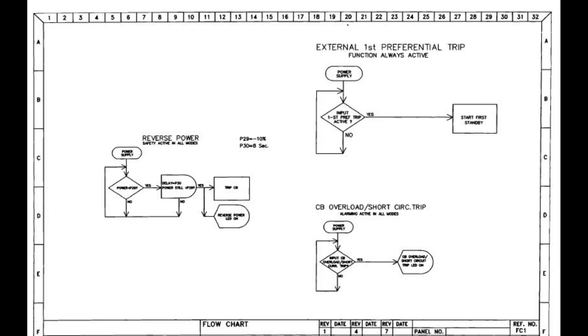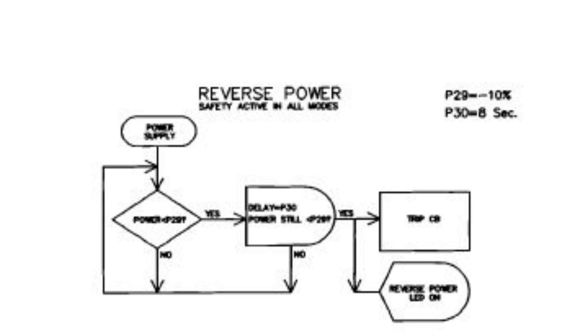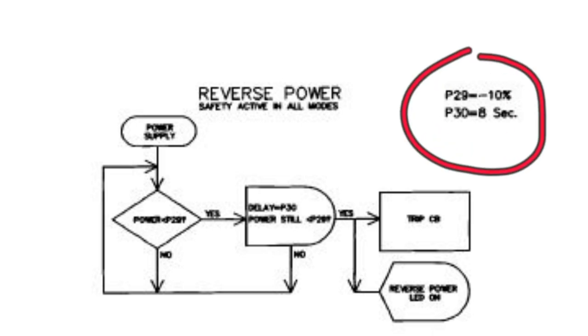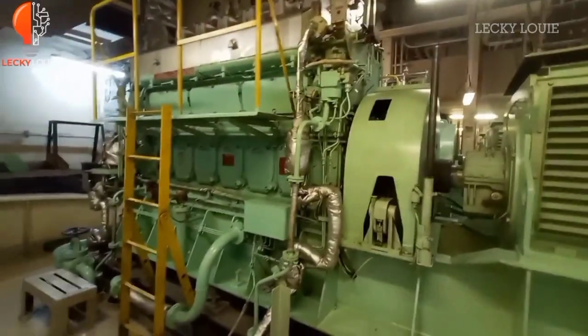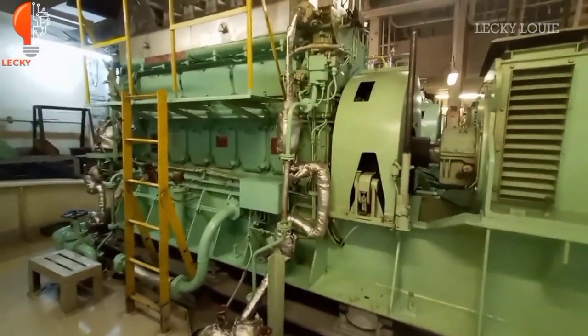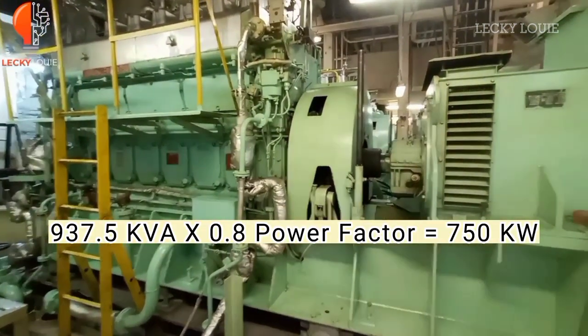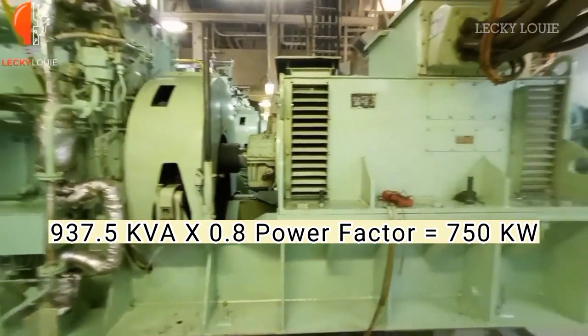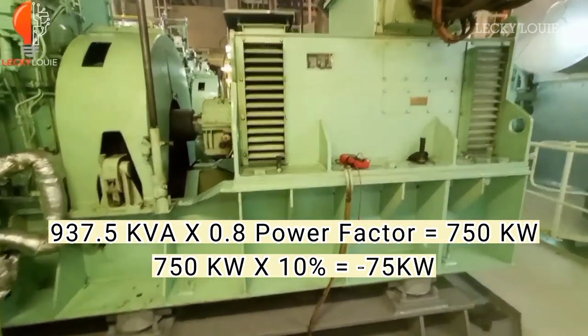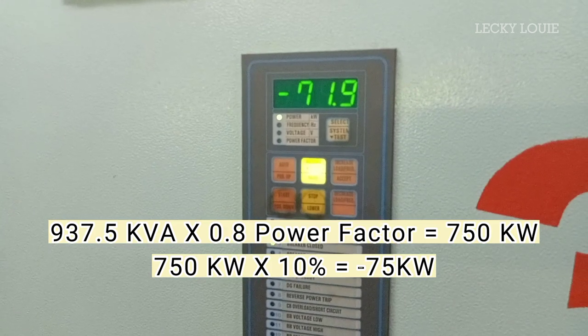To help you understand how the reverse power trip activates, let's have a look at this simple electrical block diagram. As you can see, we have set points P29 and P30. The P29 set point is negative 10% and the P30 set point is an 8 seconds time delay. Normally, the rated negative kilowatt setting is 10% of generator rated power capacity. Our generator has a capacity of 750 kilowatts, so the 10% rated power is 75 kilowatts. But since it is a reverse power, it is equivalent to negative 75 kilowatts.